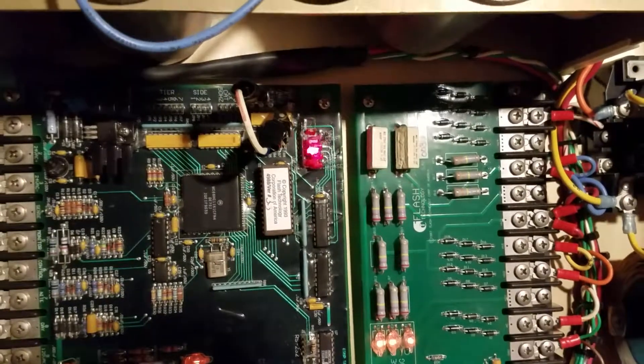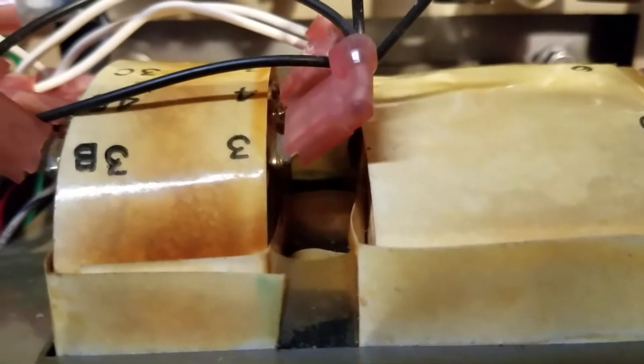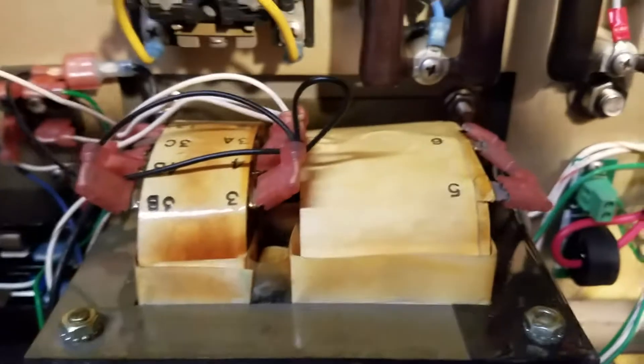Twilight does not have a relay tube, so it's just going to automatically switch over. You can kind of hear that sound I'm talking about. Here's twilight — twilight is 20,000 candela, which is the same as these dual medium intensities right here, the flash guard and the flash tech. Yeah, you can definitely hear it now. So I'll shut that off.